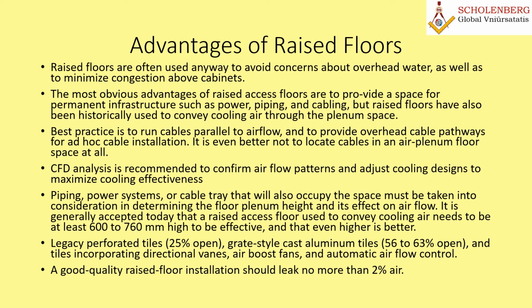And also, since all the services, say power and piping, go below the floor, there is no cluttering of overhead services. So the space above the cabinets remains fairly clean. So it has an advantage. There's no congestion above the cabinet, so any servicing can easily be done above the cabinets. The best practice is to run the cables parallel to the airflow, not in a way that can obstruct the airflow, and to provide an overhead cable pathway for ad hoc installation. And it is even better not to locate the cable in the air plenum floor space at all.